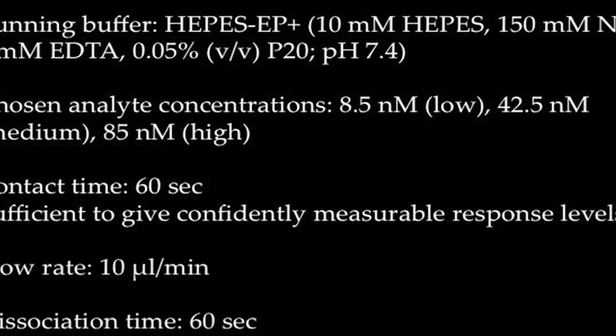Contact times of 1 to 2 minutes are usually sufficient for a binding experiment. Here, we will provide a contact time of 60 seconds at the flow rate of 10 microlitres per minute with a dissociation time of 60 seconds. An ideal regeneration condition is the one where analyte response of the same concentration is constant after repeated injections. Today, we will be using 10 millimolar glycine pH 2.5 for regeneration of the surface. We will now proceed with our binding experiment protocol.